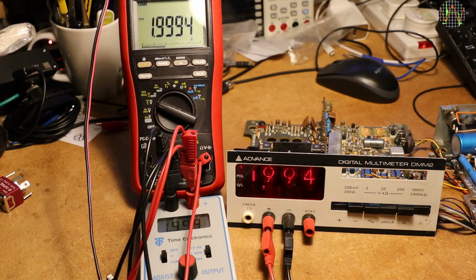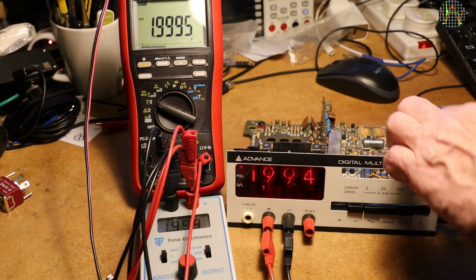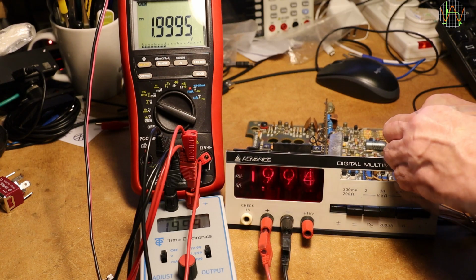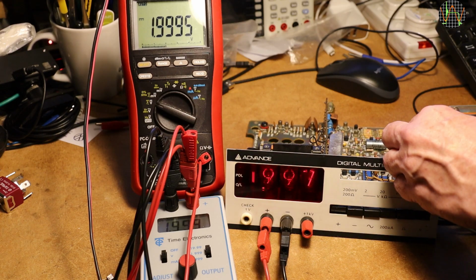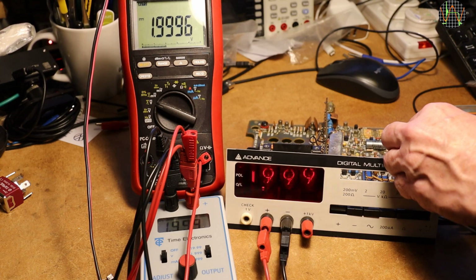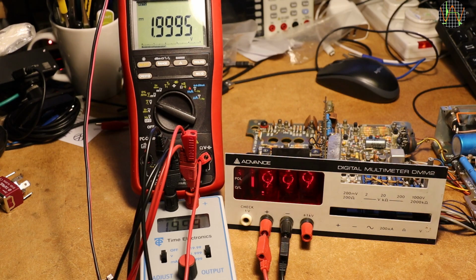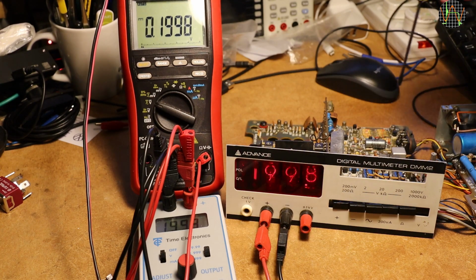Next is applying 1.999 volts and adjust another trim pot at an equally inconvenient dangerous place while the meter is open. Again, the reason for the location is that this pot is also accessible from the outside and kind of the master calibration pot. I declare that one also good enough. Next is to apply 199 millivolts and adjust the reading. Sorry, that trim pot is on the power supply board on the right and unfortunately not in view.